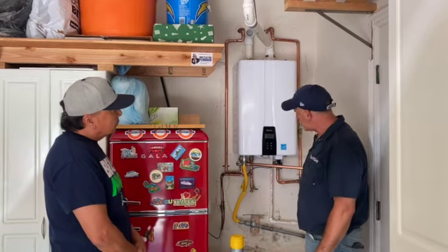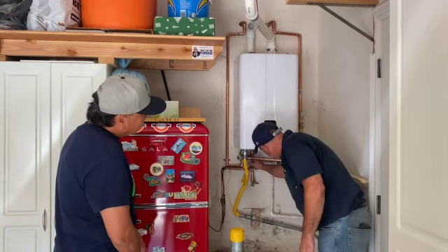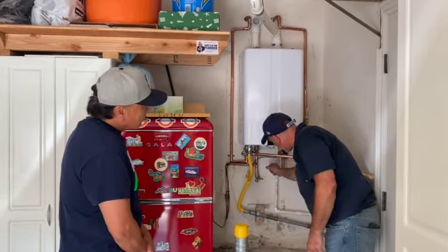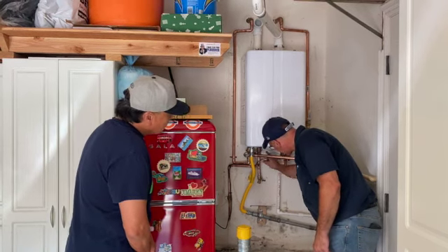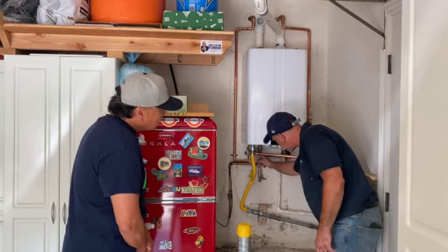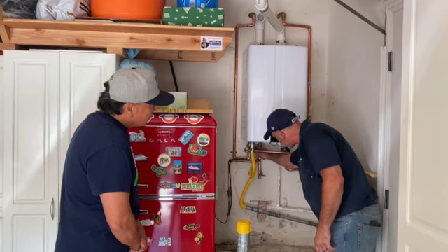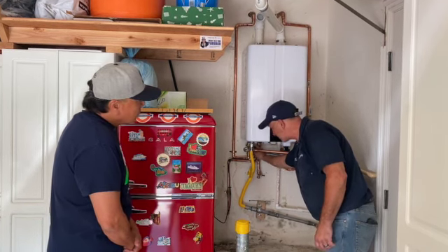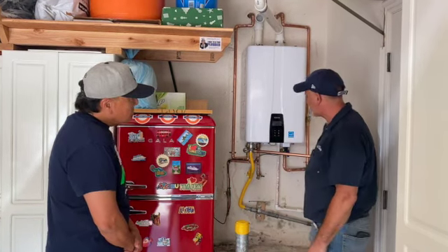It's always best to make sure that when setting up your tankless water heater, your isolation valves are in an optimal position so we can connect onto them and flush these water heaters once a year.